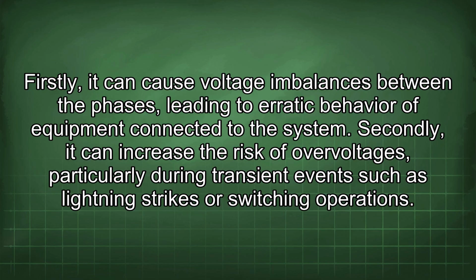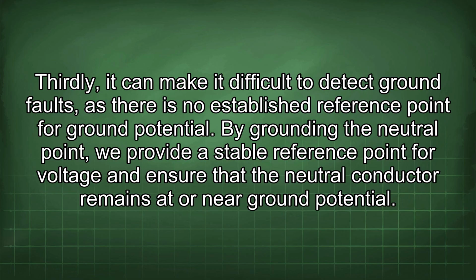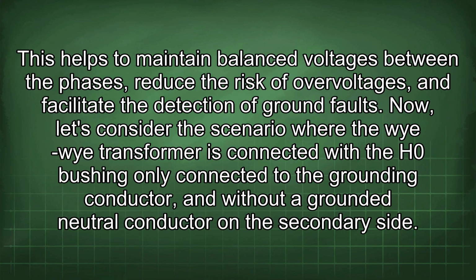Firstly, it can cause voltage imbalances between the phases, leading to erratic behavior of equipment connected to the system. Secondly, it can increase the risk of overvoltages, particularly during transient events such as lightning strikes or switching operations. Thirdly, it can make it difficult to detect ground faults, as there is no established reference point for ground potential. By grounding the neutral point, we provide a stable reference point for voltage and ensure that the neutral conductor remains at or near ground potential. This helps to maintain balanced voltages between the phases, reduce the risk of overvoltages, and facilitate the detection of ground faults.